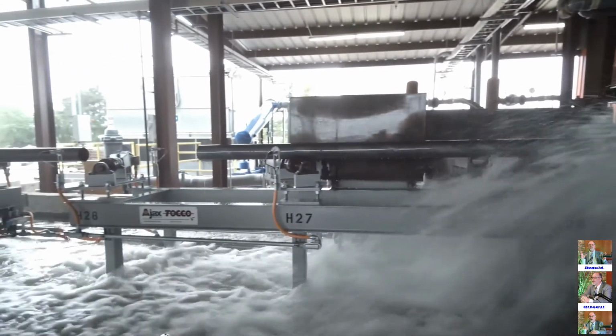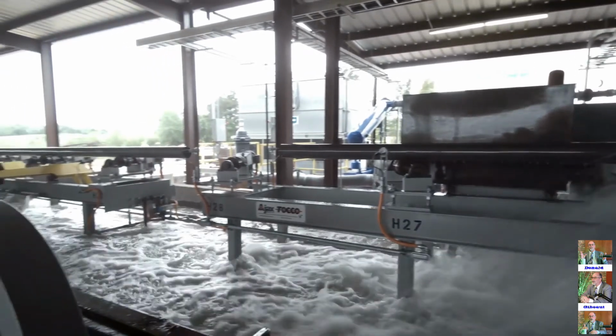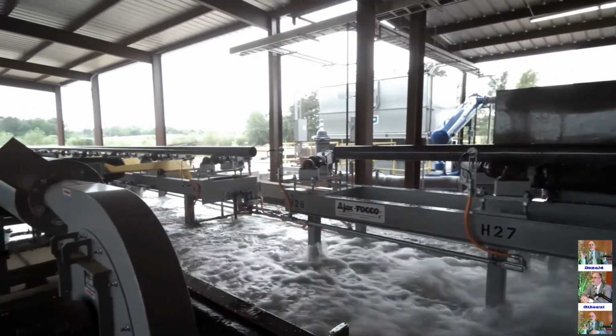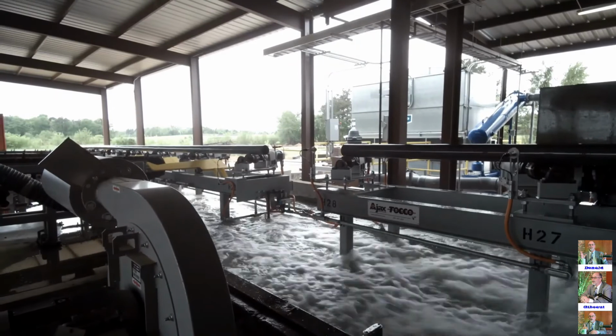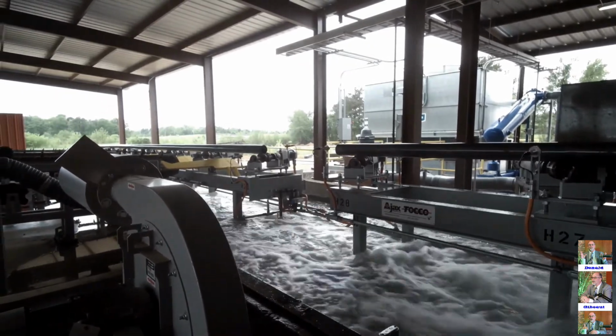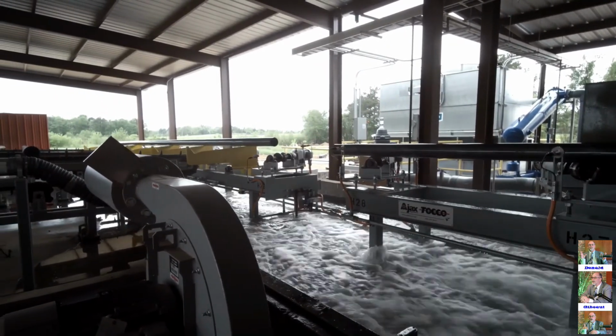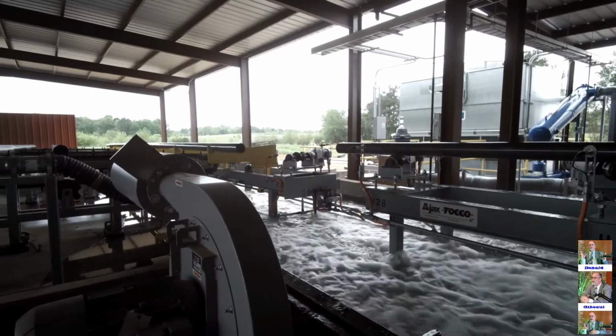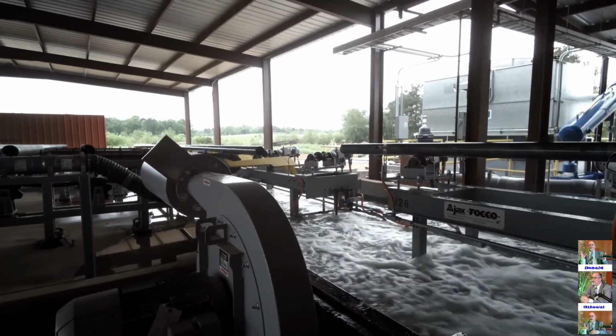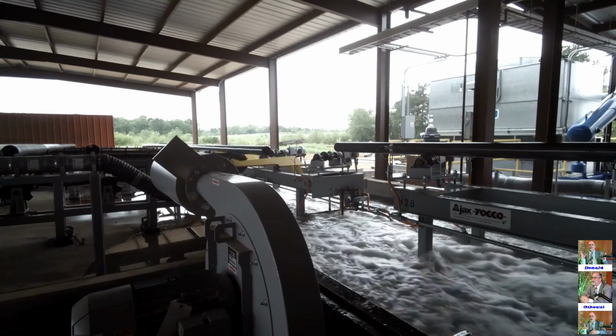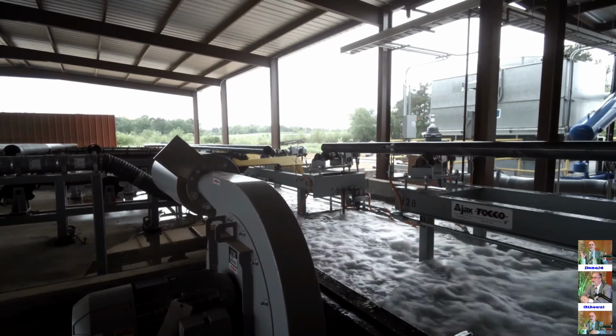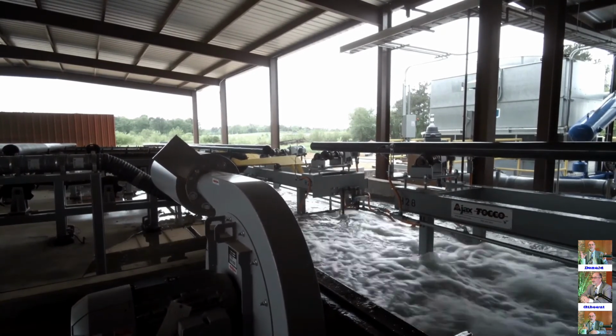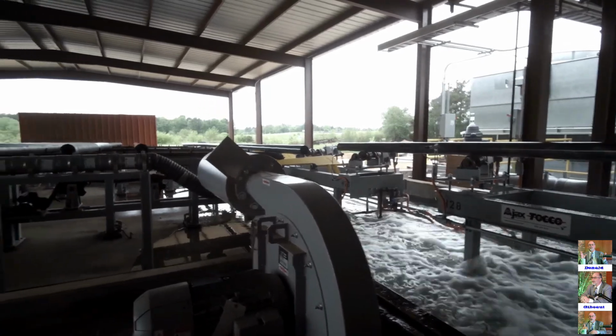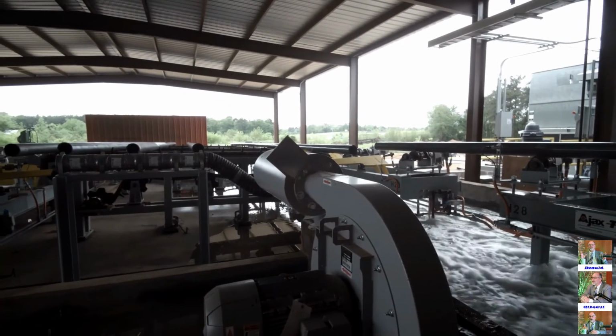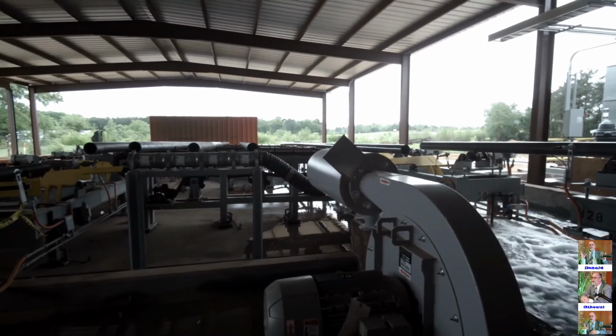The photo eyes here identify the front and the back of the part, and we speed it up so that we can take a part off with these paddles. You'll see pick up to transfer the pipe to the transfer table. There you go. Just roll down, drop down onto that drag chain. Then that table here is inclined, and you have right in front of you the ID blowout, air blowout of the ID of the tube. Very simple mechanism, very effective.